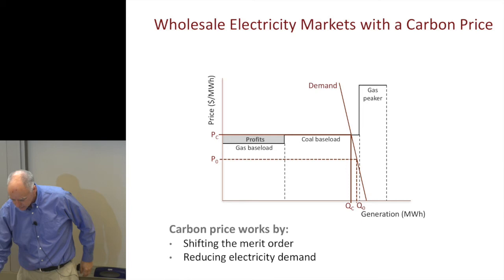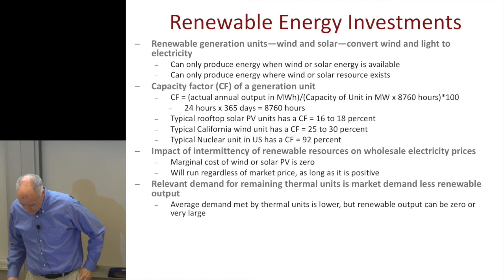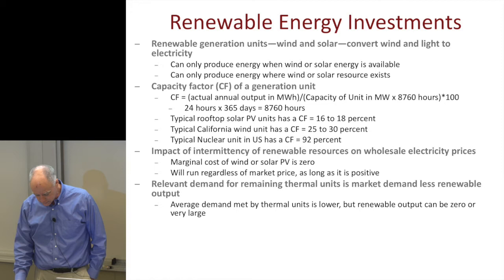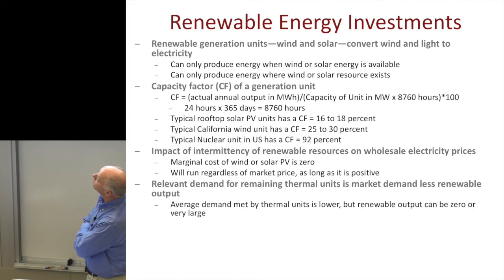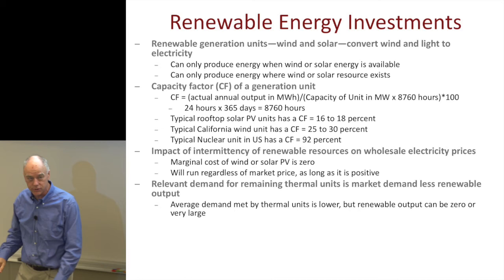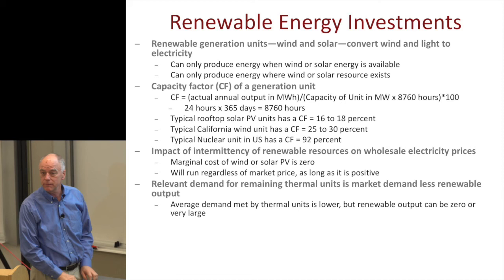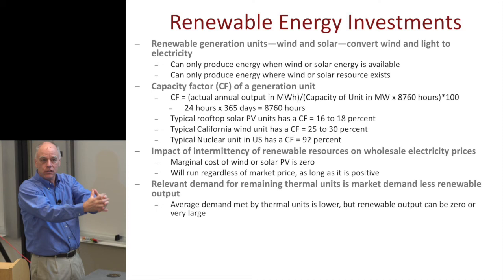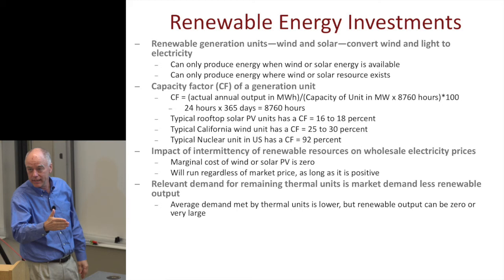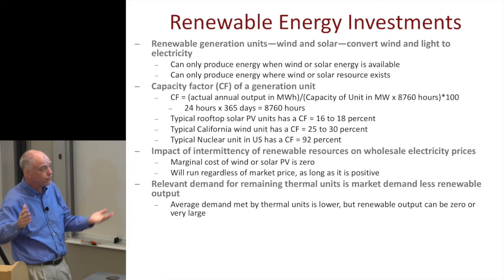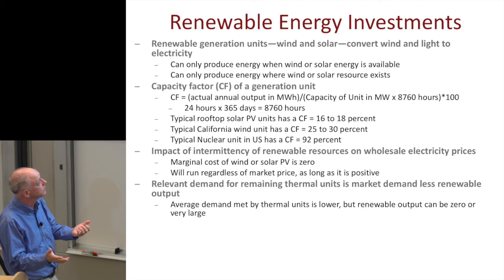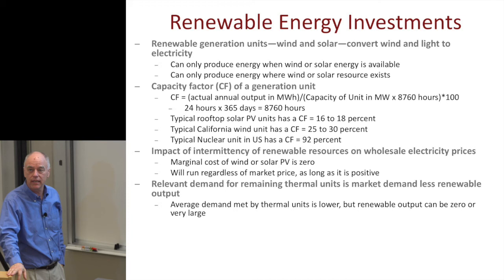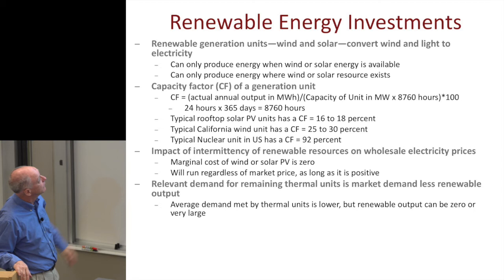Renewable energy presents a big challenge: you can only produce it when and where it's available. A key metric is the capacity factor — actual annual output divided by what the unit would produce running 24/7 all year. A typical California solar unit has a capacity factor of about 16 to 18 percent. A typical California wind unit is about 25 to 30 percent. By contrast, a nuclear unit in the United States is about 92 percent — very reliable. The great thing about renewables is that, like nuclear, they are zero-carbon, but they're also zero marginal cost.